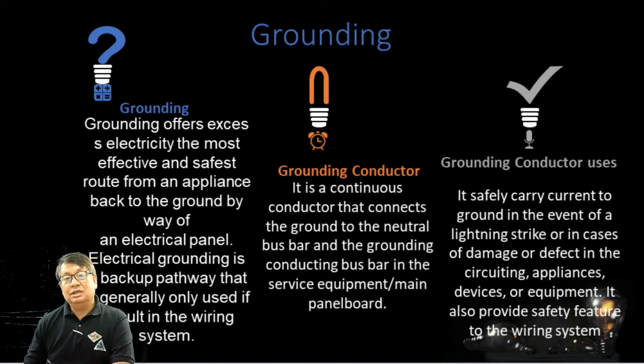So we have also this grounding conductor's uses, no? It safely carries current to ground in the event of lightning strike, or in case of damage or defect in the circuit, appliance, service or equipment, no? It also provides a safety feature in the wiring system.